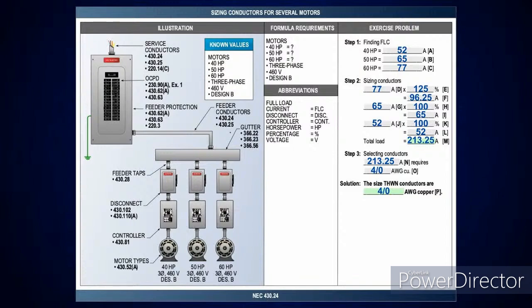You could just round down if you wanted. If I was over 0.5, I'd round up to 97. But anyway, 96 or 96.25, whatever you want to use. Then you've got 65 and 52. You take both of those at 100%. Add the total up, which gives you 213.25 amps. Go to table 310.16 and pick up the 75 degree C column. The next amperage above that is 230 amps, which is a 4/0 conductor. So if you notice, any single motor you take at 125%. If you have additional motors, you take them all at 100%, add them all up together, and size your conductor. Pretty simple.